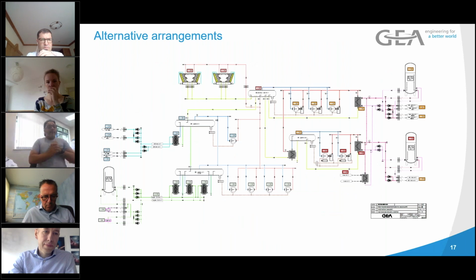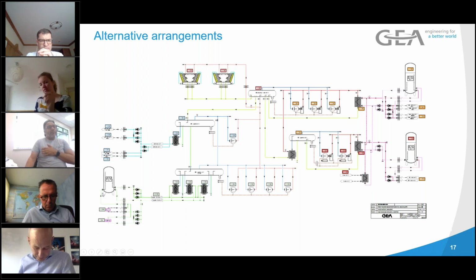This is, let's say, more of a schematic that's appropriate than my ramblings as a comic. But so here you have air conditioning, which is the air conditioning of the factory, and some water chilling. You have the process cooling with the green pipes and a buffer tank. The buffer tank is to take the spikes out of the process before it hits our refrigeration plant. You can see the compressors here, and then we reject the heat via some condensers up on the roof.